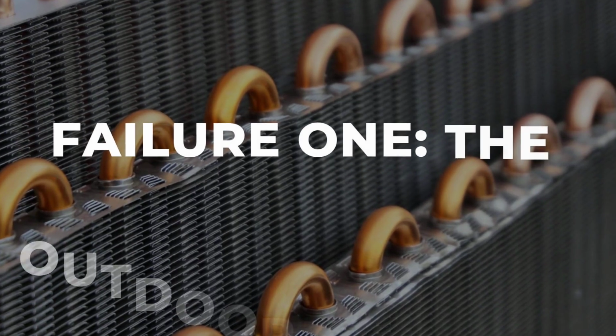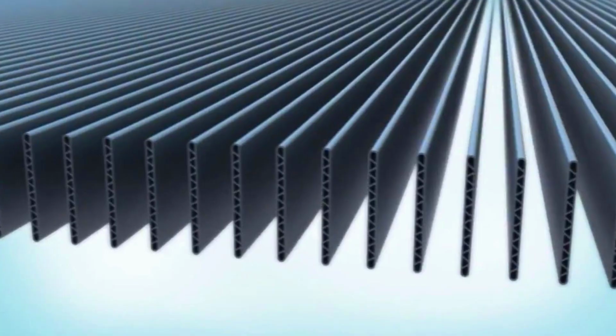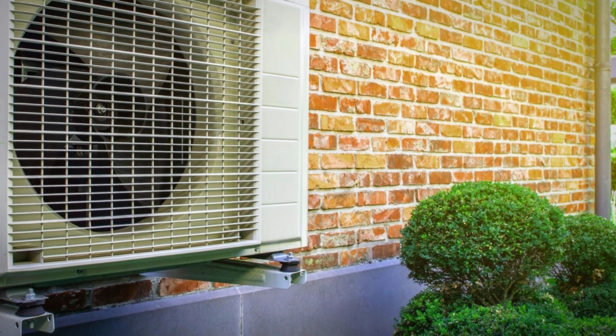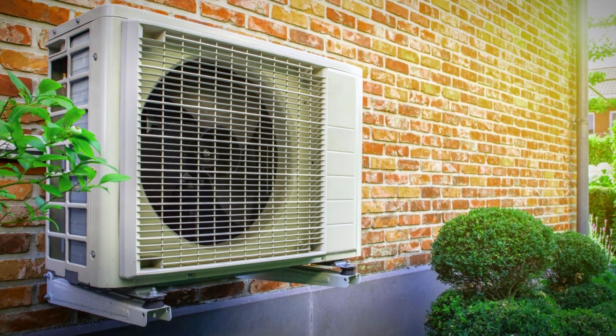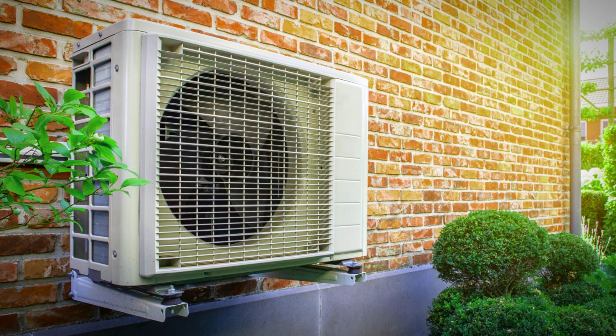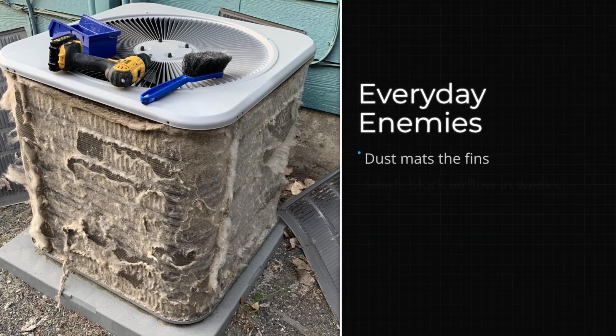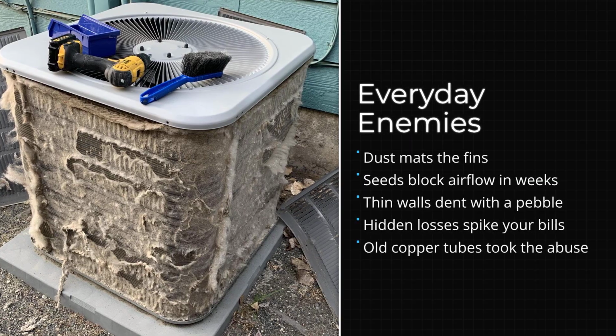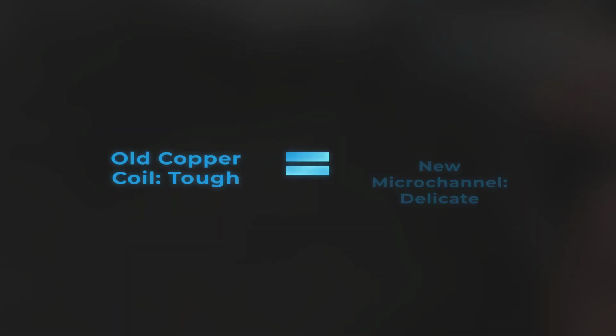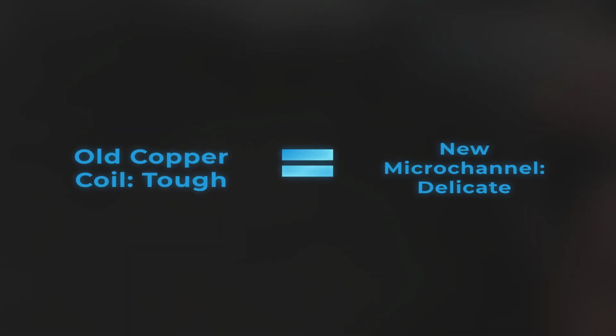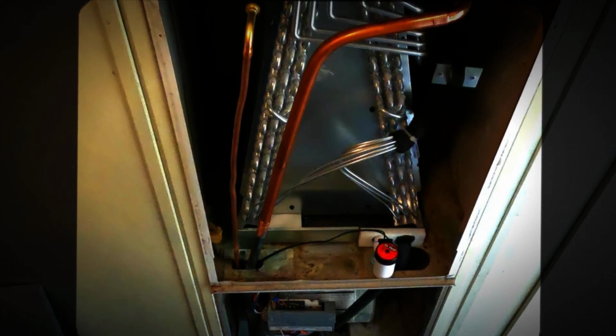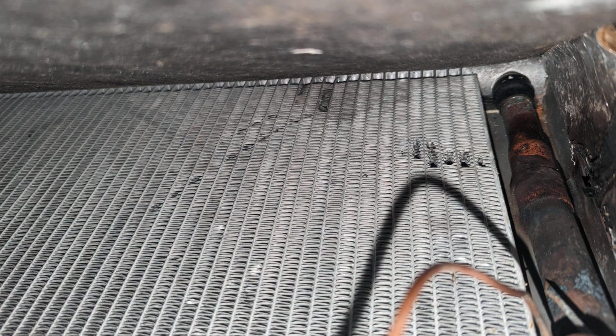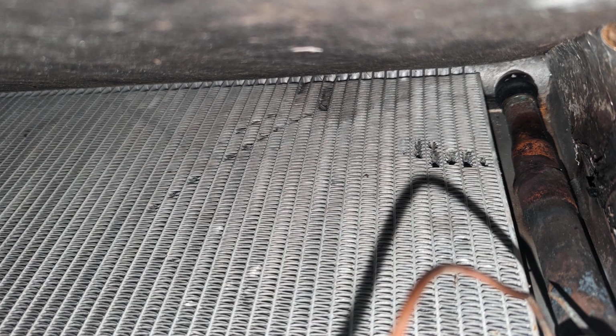Failure 1, the outdoor coil face. Microchannel packs dense heat transfer area into a compact surface, but those fins and passages are vulnerable to the real world. Dirt loading, cottonwood seeds, lawn debris, a pressure washer held too close, a weed eater that throws a rock. Any of these can damage passages that were never designed to tolerate rough handling. The old chunky copper and aluminum coils could take abuse. The new ones punish neglect and punish accidents.